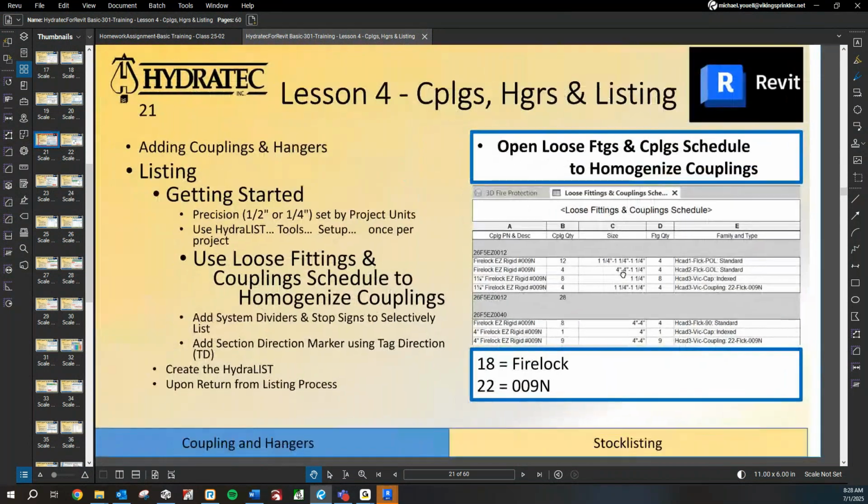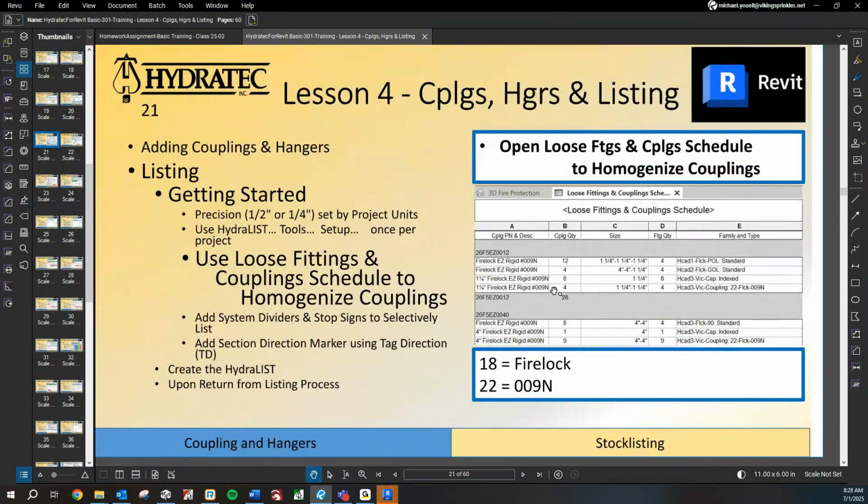So we did that to make it much easier for you guys to model this thing. When you draw an 1.25 pipe into the side of an 1.25 pipe, it puts a T there. It knows that it's all the same sizes, so it looks like a T, and it puts the couplings on that T. And the purist of Revit people would say, you can't do that. That's actually 4 objects. It's a T and 3 couplings.